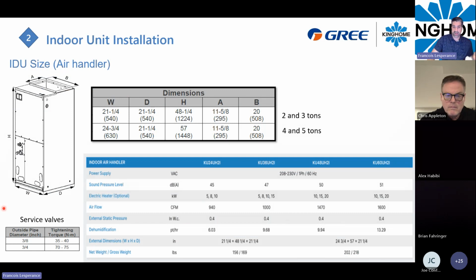Here we have all the sizes of the units. What's really important to know about this kind of unit is that you have service valves on the indoor unit as well. That's a good addition to this kind of installation, because on the piping side you will flare inside and flare outside, so no welding. Also, you only make your pressure test and vacuum in the piping, not even in the coil. That's really awesome with this kind of unit, because you will save so much time installing it.